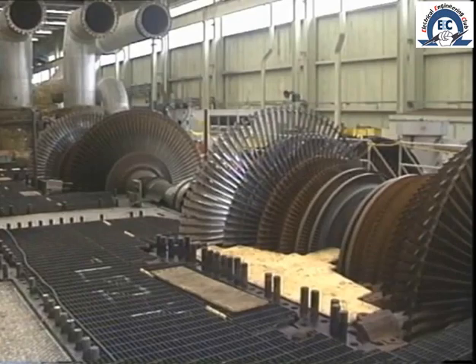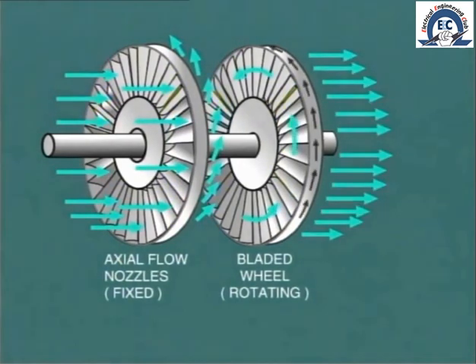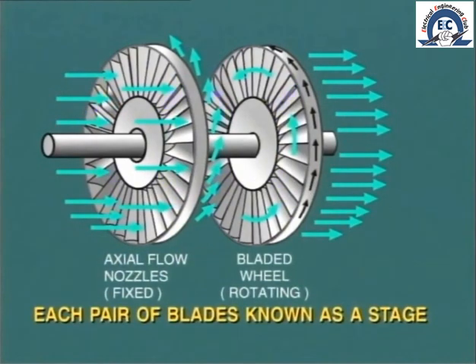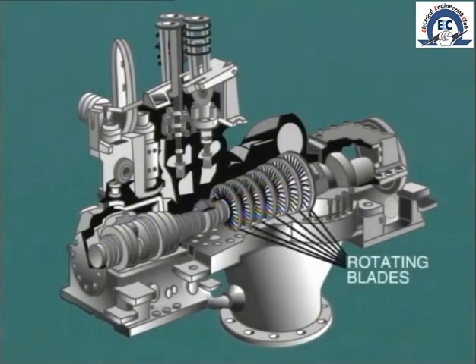As we know, the heart of the turbine — the bit that makes it work — is the relationship between the fixed and moving blades. The fixed blades guide the steam onto the moving blades. As the steam passes through the moving blades, it causes the disc to which they are attached to rotate, and consequently the shaft rotates. Each pair of stationary and associated moving blades are known as one stage. Most steam turbines contain many stages of blading. In this example of a single cylinder machine shown here, we have seven stages. And do not forget: the stationary blade is always ahead of the moving blade.